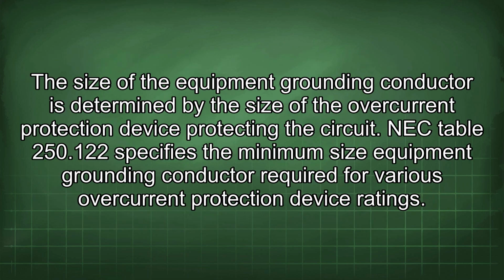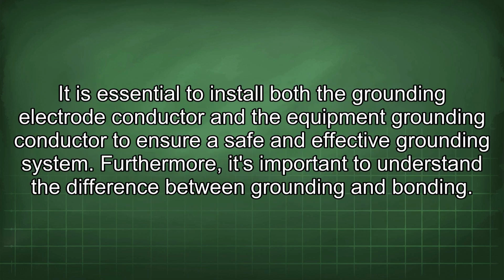The size of the equipment grounding conductor is determined by the size of the overcurrent protection device protecting the circuit. NEC Table 250.122 specifies the minimum size equipment grounding conductor required for various overcurrent protection device ratings. It is essential to install both the grounding electrode conductor and the equipment grounding conductor to ensure a safe and effective grounding system. Furthermore, it's important to understand the difference between grounding and bonding.